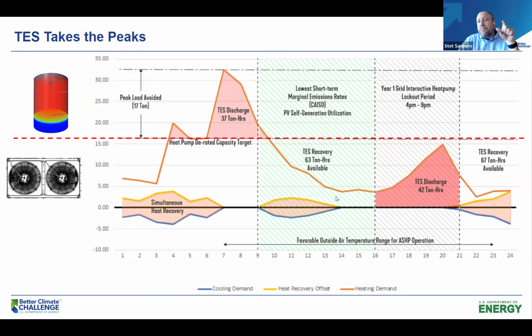And then as you go into the middle part of the day, as your peak heating load goes down, everybody's turning on equipment, life is happening inside your building. Now you can recharge that tank. That thermal storage is going to give you a lot of flexibility, both to meet the peak load and downsize my equipment, but it also lets us run our equipment in hours where we don't need heat, but we can store it when the grid is cleanest because of solar, or as Nora mentioned earlier, if you install solar on your own building, you want to make the best of it.